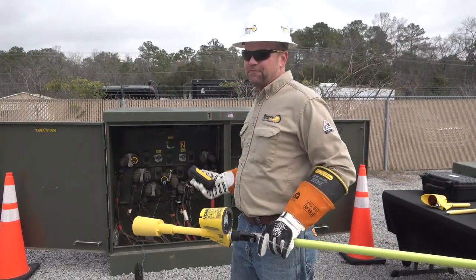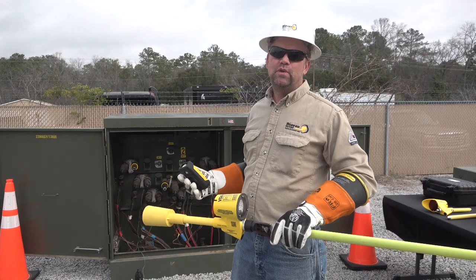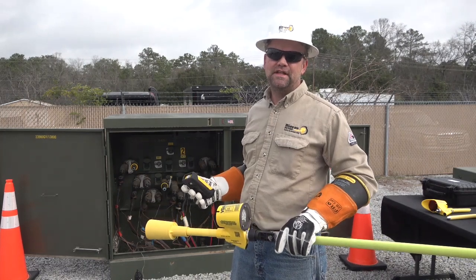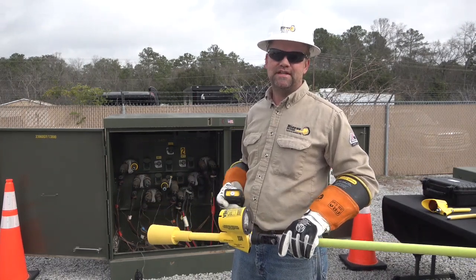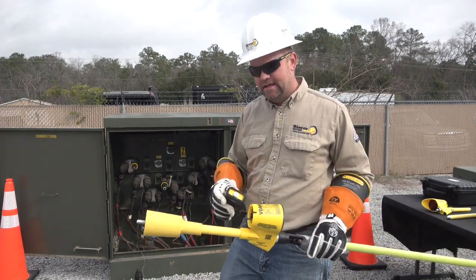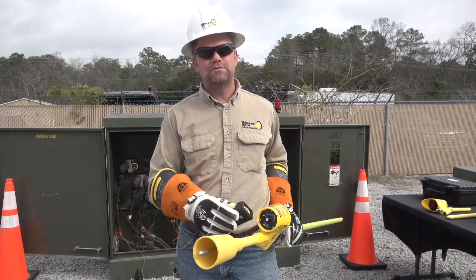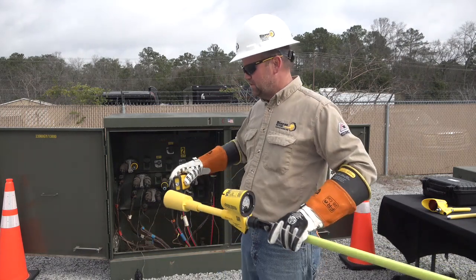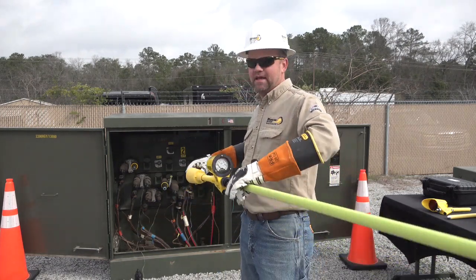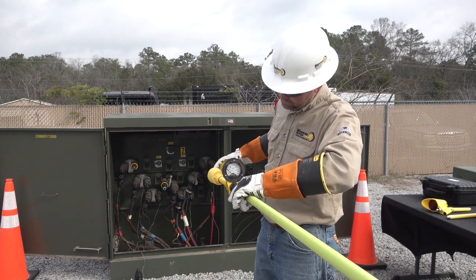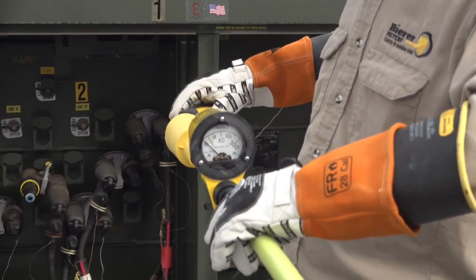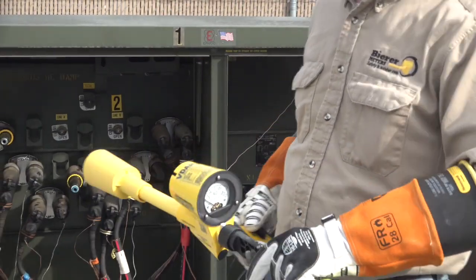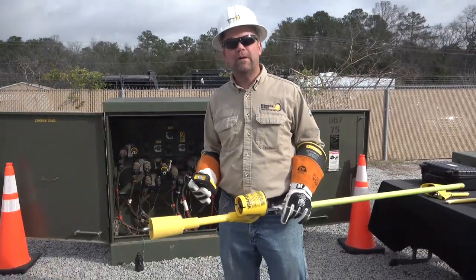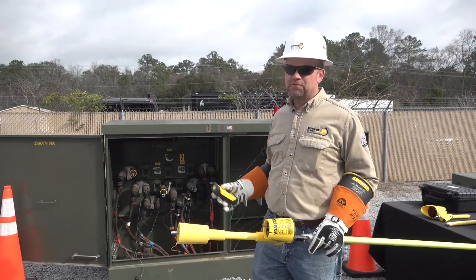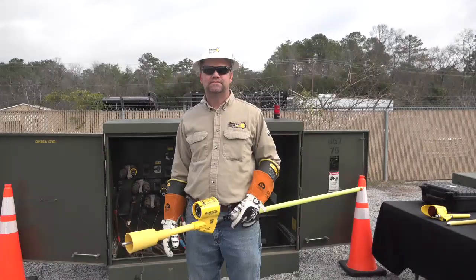Okay, I've already tested for de-energized. I want to verify that the tool is working properly and make sure the needle's not broken, in case something happened between testing it the first time. Again, I still have the tool in the first on switch position. I'm going to depress my HHPS and make sure I get a needle deflection every time I touch the end of the bushing adapter probe. So that verifies that the tool is working properly and that cable stood off is de-energized.